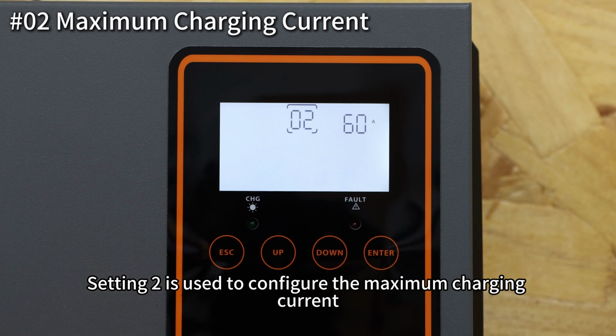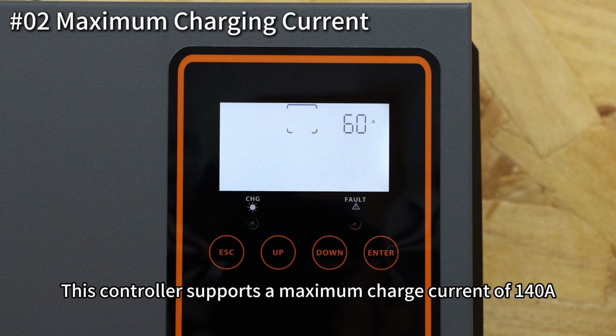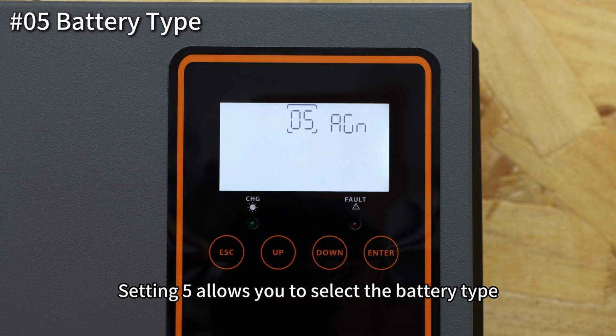Setting 2 is used to configure the maximum charging current. This controller supports a maximum charge current of 140 A. Setting 5 allows you to select the battery type.